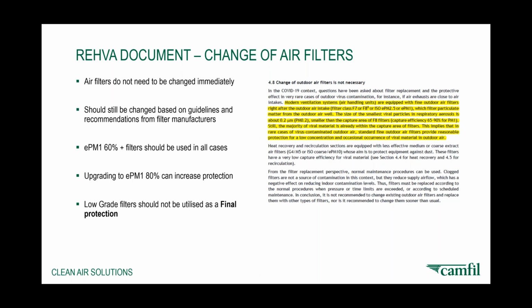On recirculation, they've said, and most systems unfortunately have low-grade filters, what would have been G4 or M5 or ISO coarse, now ePM10 filters, in the recirculation systems, and that was primarily just to protect against dust going back up to the ventilation system. It wasn't for protection of people, just for protection of the actual HVAC system. So they're recommending that a low-grade filter should not be used as final protection, or low-grade filters should not be used on recirc.